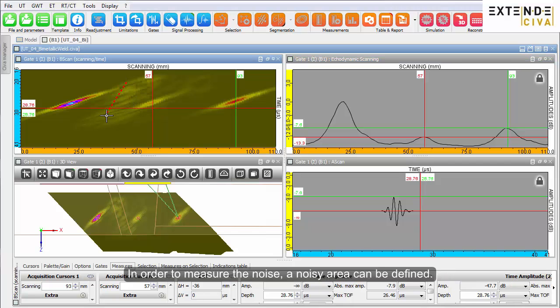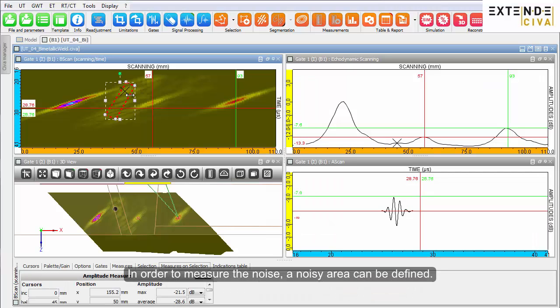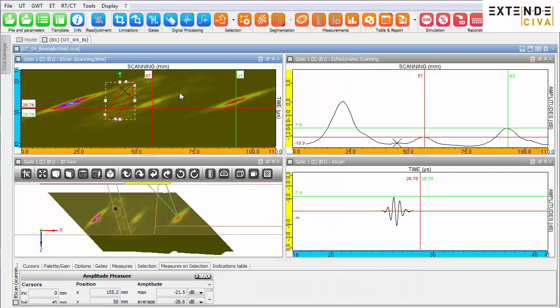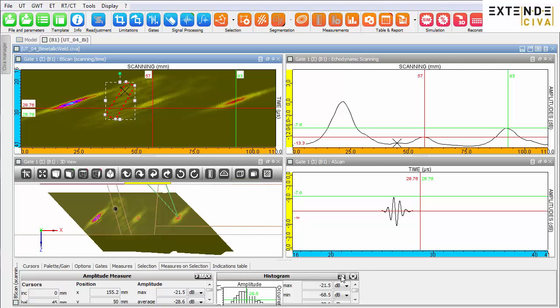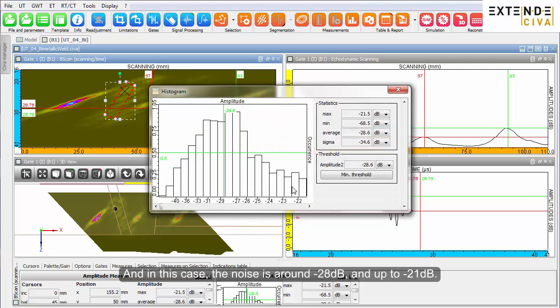In order to measure the noise, a noisy area can be defined. Then, the amplitudes in the area can be displayed as a histogram. And in this case, the noise is around minus 28 dB and up to minus 21 dB.